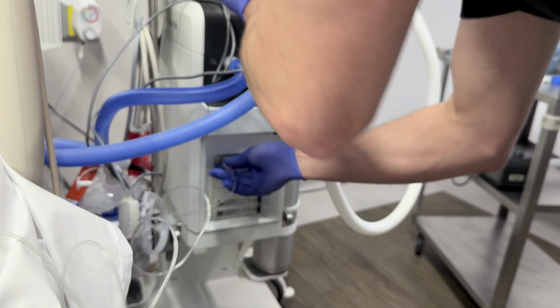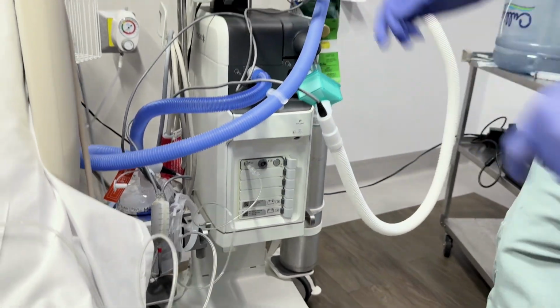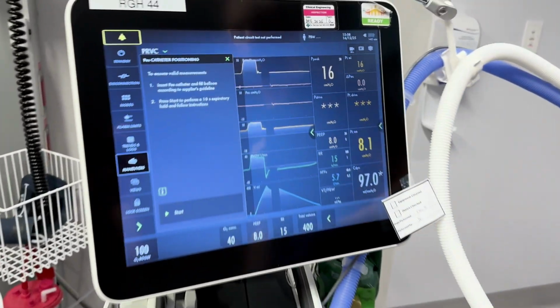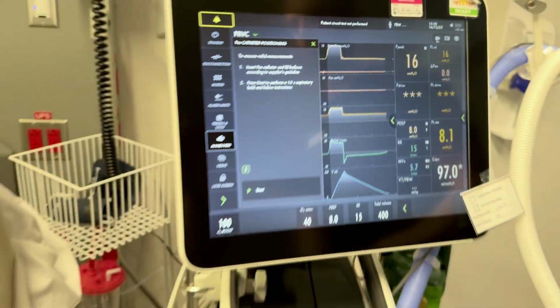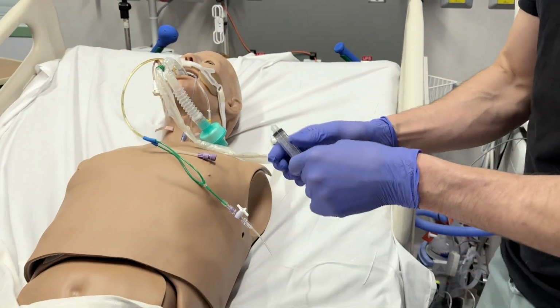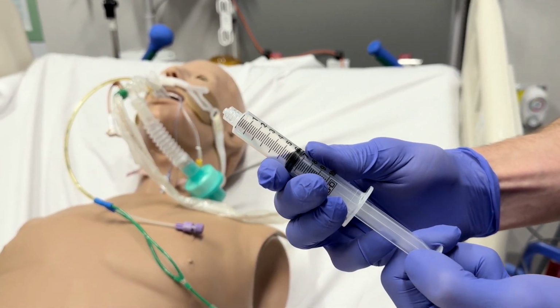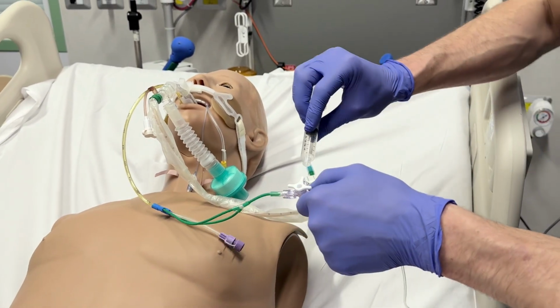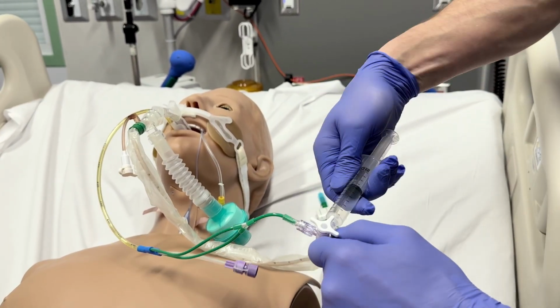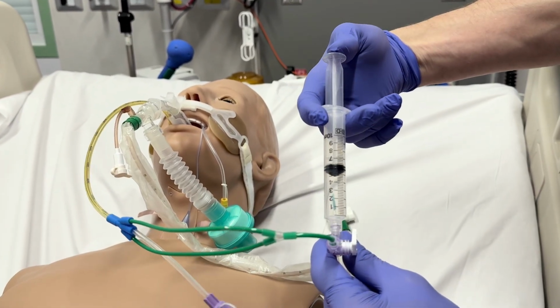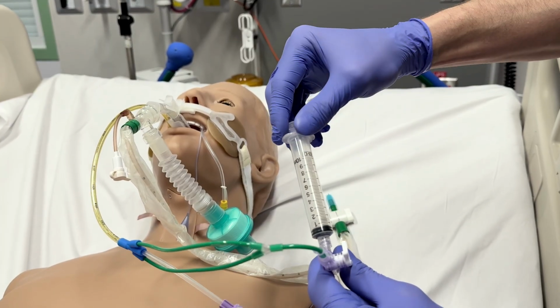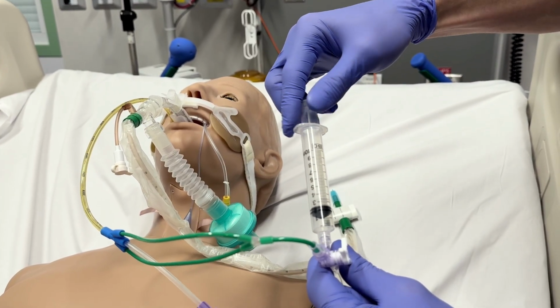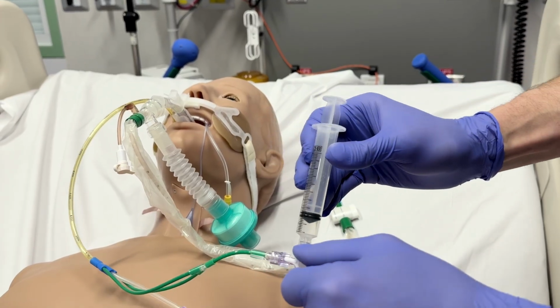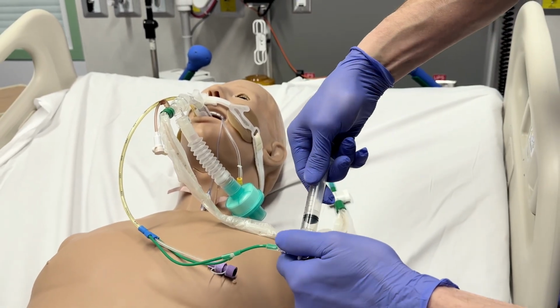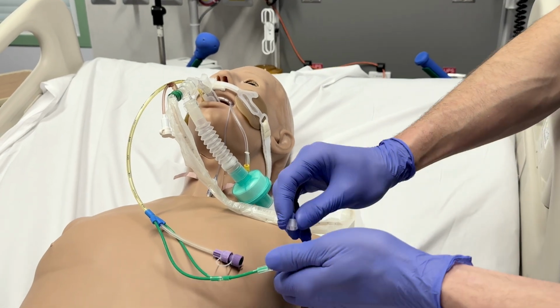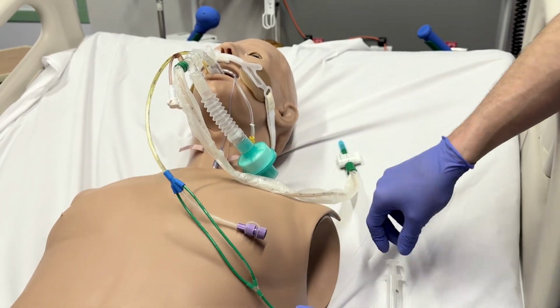While the stopcock is open to atmosphere, allow at least 1 to 2 breaths and confirm the esophageal pressure waveform on the ventilator is flat and measuring 0. Withdraw 6 milliliters of air into the syringe and connect to the 3-way stopcock. Insert 6 milliliters of air into the balloon, then withdraw 2 milliliters, leaving a total of 4 milliliters in the balloon. Turn the stopcock tap 180 degrees so it is closed to the syringe, but open to the ventilator and catheter. Remove the syringe and replace the cap.